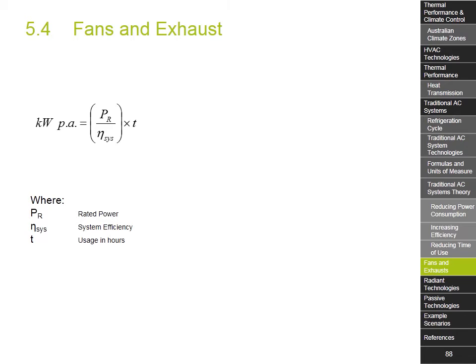Fans and blowers can essentially be considered as pumps where efficiency is concerned. Both work by directing a volume, in this instance a gas, through changes in pressure, and in both cases efficiency is an expression of the ratio of power gained by the volume to the shaft power supplied.